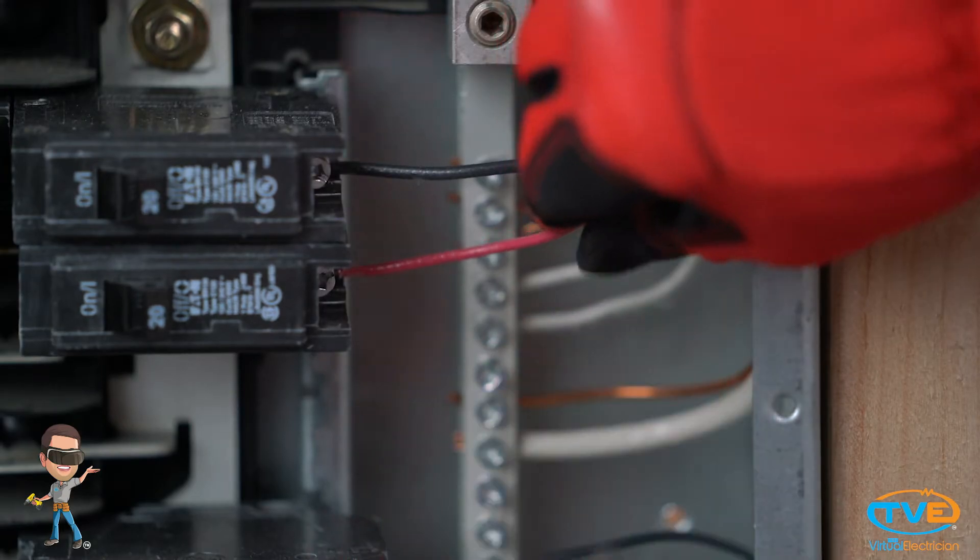The other thing that may be happening is you have a loose connection. Remove the wire, cut off the burnt stuff, and reconnect the wire with a tighter connection.